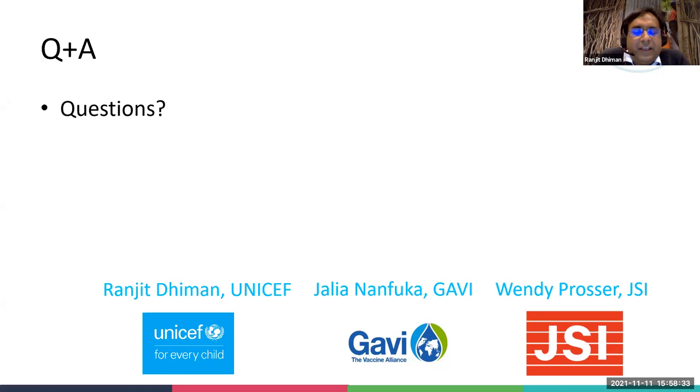On this, I was thinking about a COVID-19 specific response to this temperature problem. I can quote what was done in one country, for example, because this is a situation every country is struggling with. An SOP was developed in that country to say we will use 30 DTR for COVID-19 monitoring, and then we will use RTM data, everything end to end. Since the vaccine is going to be in the country from the time of arrival to the time of vaccination for not more than 60 days, and it's going to be consumed by that time, the idea was to use 30 DTR.